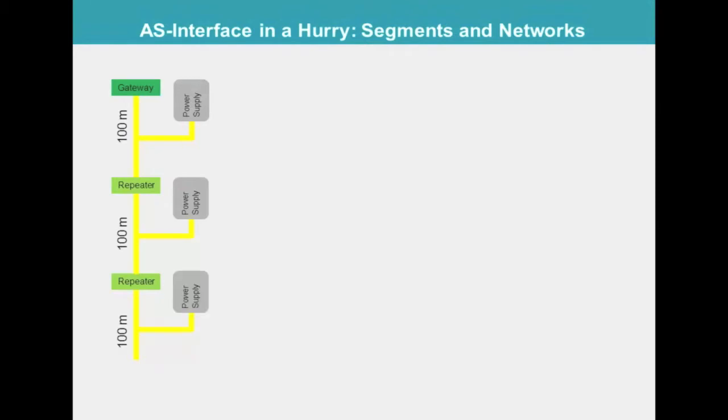This is a valid 300 meter linear network. To simplify the drawings, we will assume power supplies to be present, but will no longer show them. Let's start with a linear network and add a repeater here. This is allowed as long as the first segment containing the gateway is no more than 100 meters long.